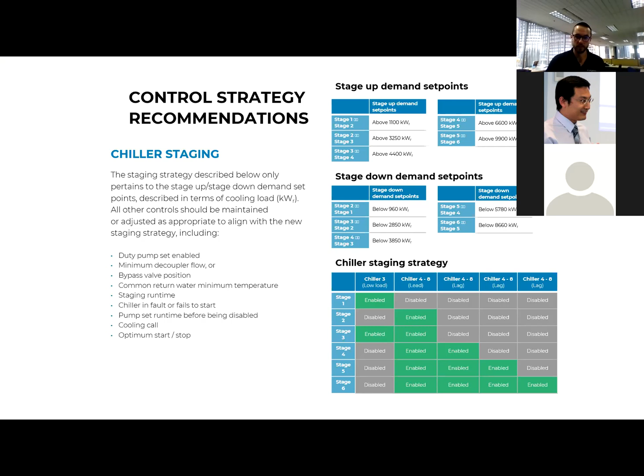So here's the COP, the optimal COP for the plant at any one time. You can see here, this is the low load chiller operating by itself, then the high load chiller comes on. This is the low and high. So that's that stage 3 in this region here, between about 3,000 and 4,000 kilowatts or 3 and 4 megs of cooling. And then you can see here, as this would be the 2 high load chillers, it's tried to bring the low load back on there.